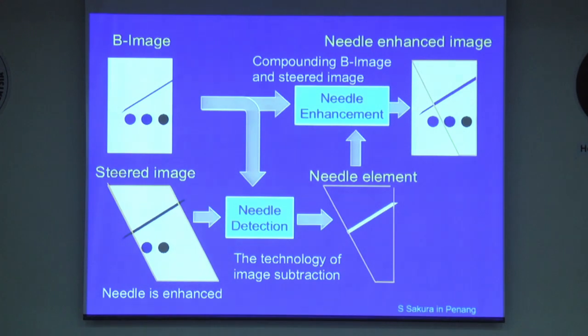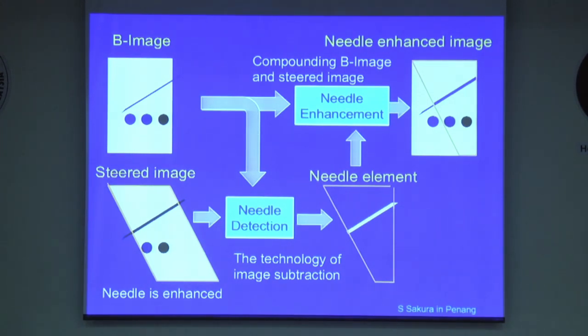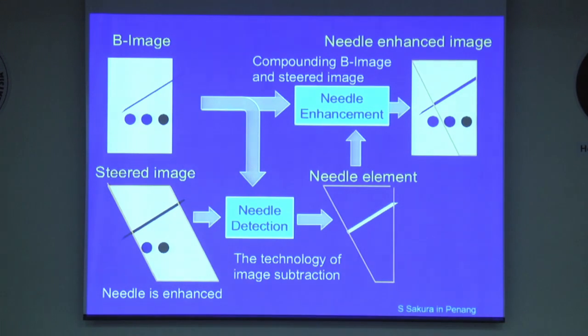To overcome this situation, many ultrasound companies have developed ways to create a needle-enhanced image. I'm not entirely sure I understand it very well, but let me try explaining the basics. With simple B-mode, the reflected echo from the needle goes away from the transducer, so that you could barely see the needle — only tissues.